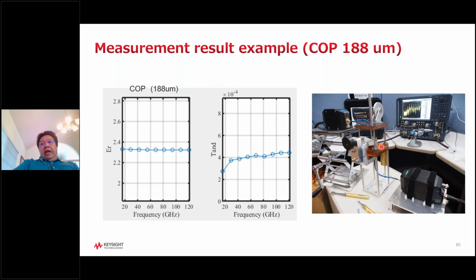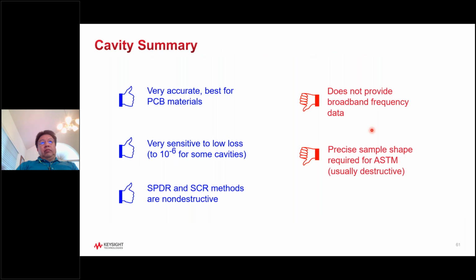This picture shows the actual measurement setup. You know, the heads down here, the other ones up here, moving up and down. And of course, before doing that, we had to do a two-port calibration at the end of the cable here and here first before we connect to these fixtures. So the summary of this fixture, basically the cavity fixture is the best for low loss material. Actually, this is the only solution that's available if you want to measure really, really low DF values. The limitation for this is that it has limited frequency points.